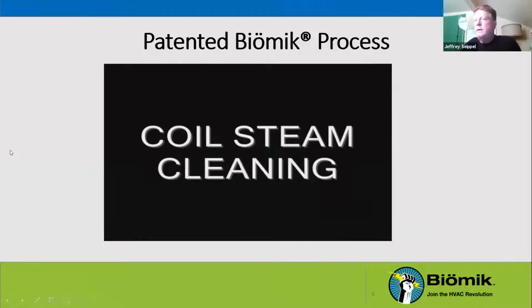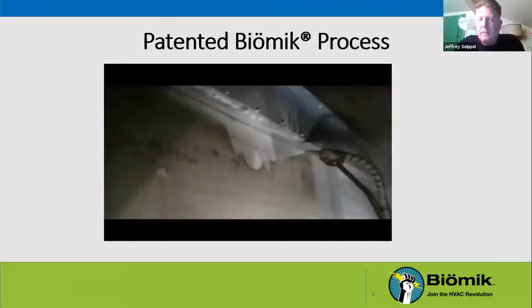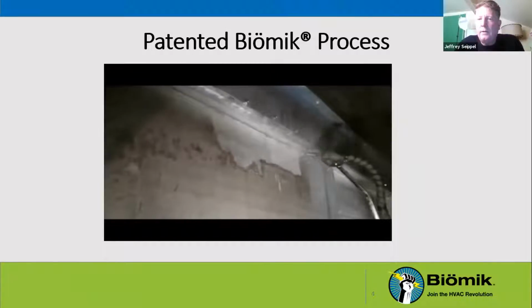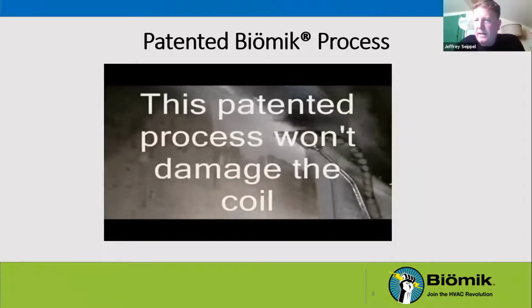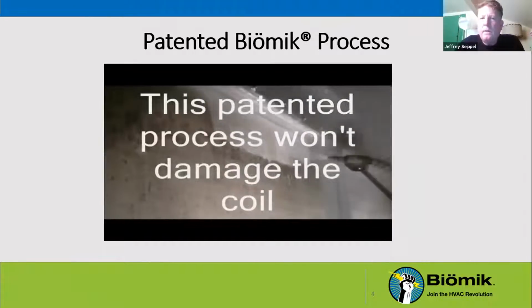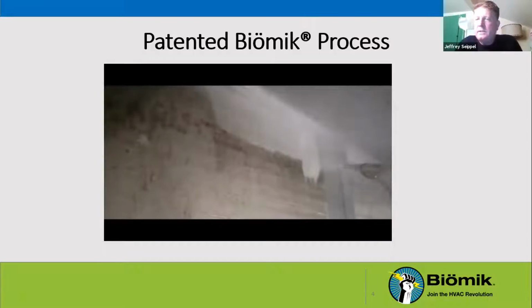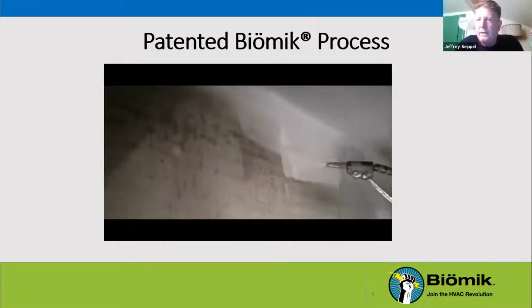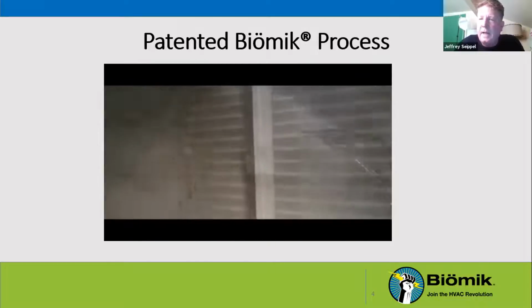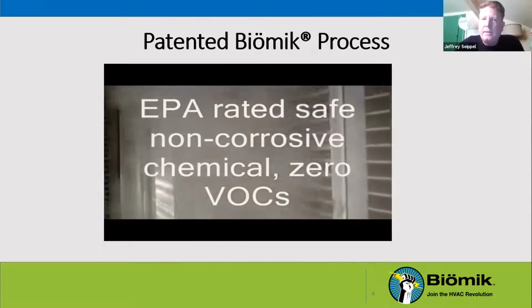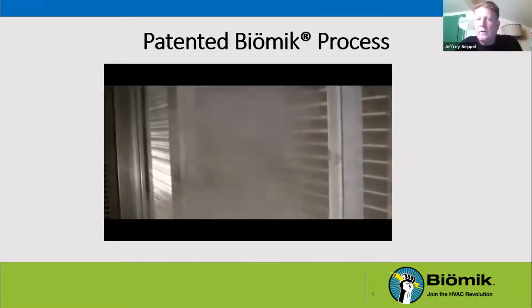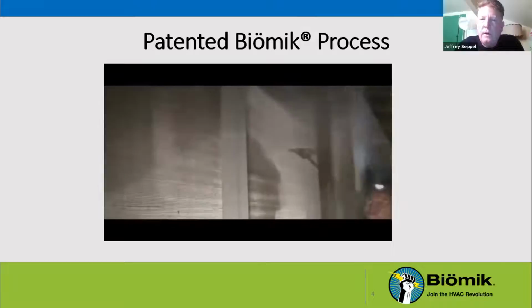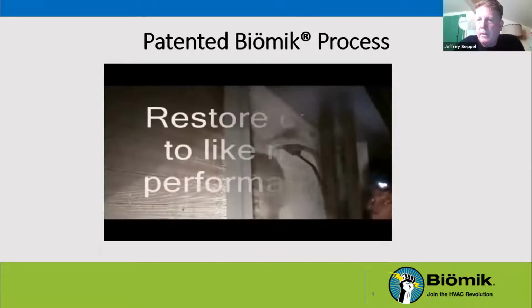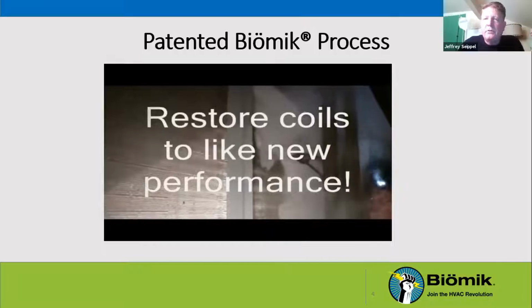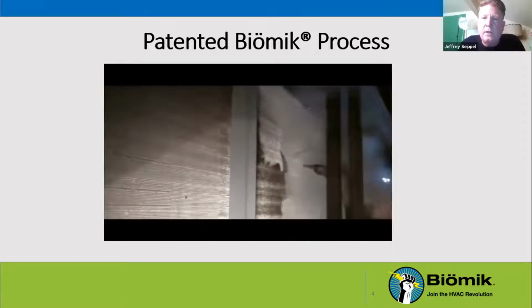The other part of the process is using steam. Once the probiotics loosen the biofilms in the coil, you have to then get all that material out of the coil. So we use a steam system. We're shooting water at 280 degrees at 1500 PSI, which gives us the ability to deeply clean the coil without damaging anything. Coils, the fins on coils can be delicate, especially if they're older. So being able to clean thoroughly but not do damage is a bit of a trick. You have to have just enough force, but not too much.